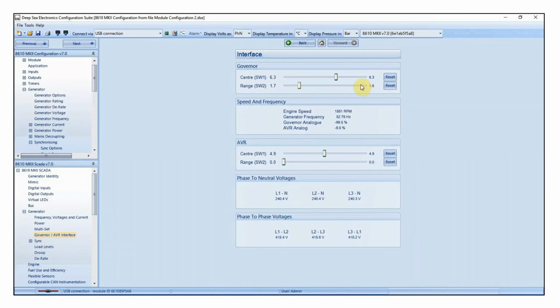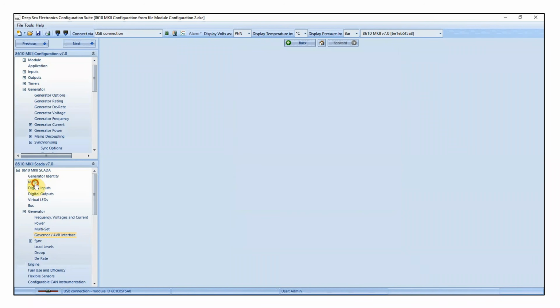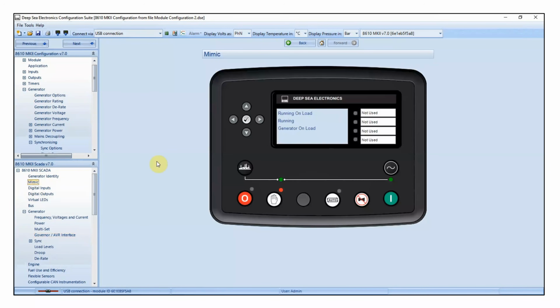You'll see as you keep increasing switch 2, eventually the governor analog percentage will go from 100% and start decreasing. Now, in this example, I've accidentally overshot the 80%. That's not a problem. To combat this issue, I just decrease the switch 2 value. So keep in mind, increasing switch 2 decreases the governor percentage, decreasing switch 2 increases the governor percentage. So I just keep increasing switch 2, decreasing switch 2 until I get 80%. You may not get exactly 80, that's fine, as long as it's somewhere between 75 and 85%, which I've got here. So all I'm going to do now is open the genset breaker and stop the generator.